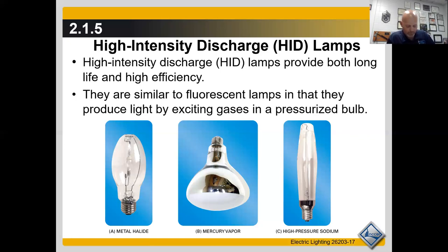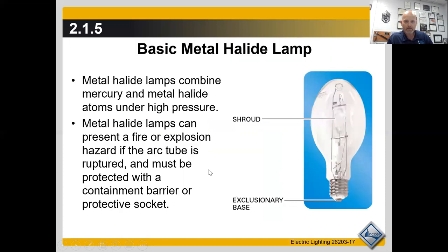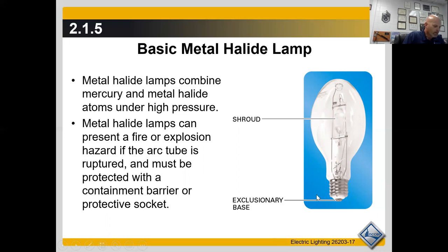Like fluorescent lamps, HID lamps must be used in matching fixtures specifically designed for that lamp and wattage. There are three types of HID lamps: mercury vapor, metal halide, and high-pressure sodium. Metal halide lamps are very energy efficient with 80 to 150 LPW, excellent color rendition, long service life of more than 20,000 average hours, and good lumen maintenance. The excellent color rendition of metal halide is a test question point.